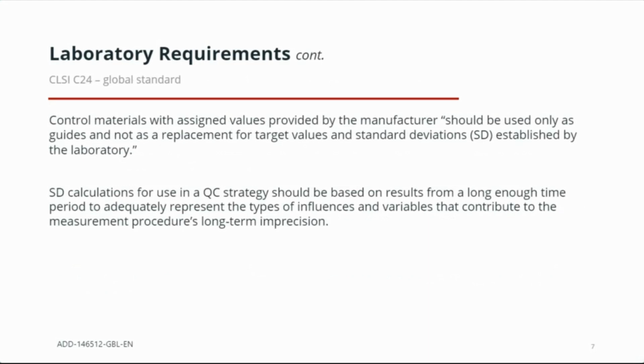The Clinical and Laboratory Standards Institute document C24 is Statistical Quality Control for Quantitative Measurement Procedures. It states control materials with assigned values provided by the manufacturer should be used only as guides and not as a replacement for target values and standard deviations established by the laboratory. The SD calculations for use in a QC strategy should be based on results for a long enough time period to adequately represent the types of influences and variables that contribute to the measurement procedure's long-term imprecision.